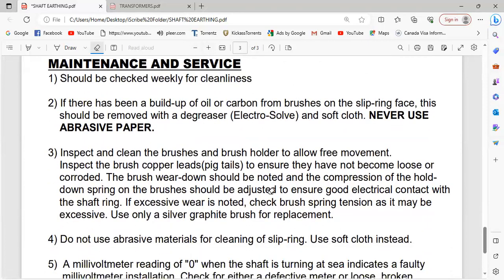Maintenance and service, as I said, is a weekly routine. You should include it in your Saturday routines. Be very careful. Number 2, if there has been a buildup of oil or carbon from brushes on the slip ring face, this should be removed with a degreaser and a soft cloth. Never use emery paper, because you can damage the surface of that ring. Point 3, inspect and clean the brushes and brush holder to allow free movement. You'll be having your silver graphite dust and all that. Please make sure that all that is cleaned.